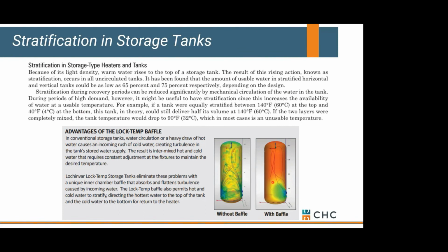If you order a tank without baffles, you might get a lot of stirring going on inside the tank that dilutes it pretty quickly. That would simply mean that your heater is going to have to run more often to recover it. But one question that always comes up is how much usable water am I going to have in this storage tank? Let's say it's a 100-gallon tank. Industry standard tends to be about 70%. Lochinvar is claiming 80%. So a 100-gallon tank, we can send 80 gallons out to the system before we have to turn on our water heater and recover the storage tank.